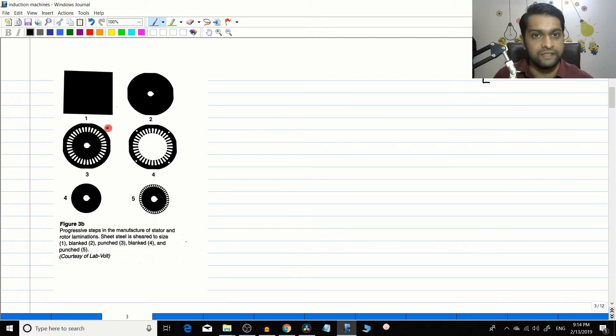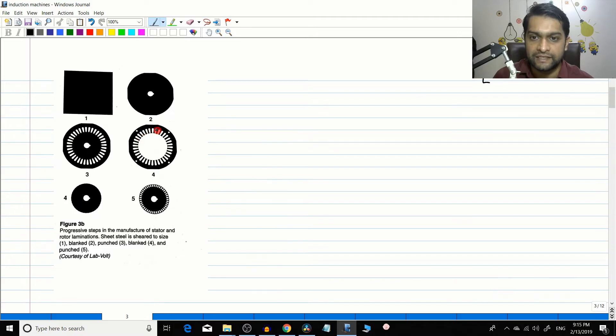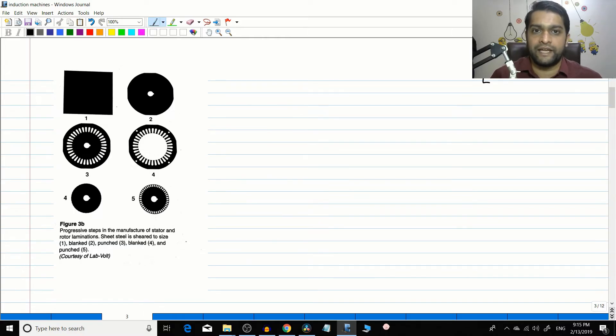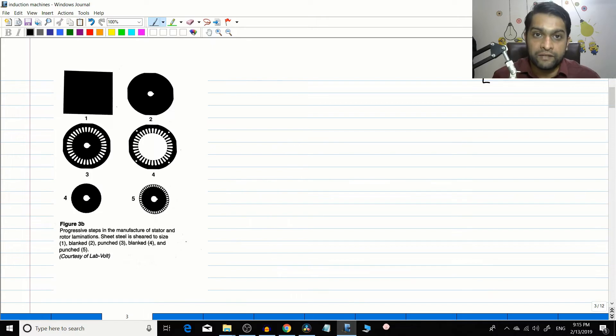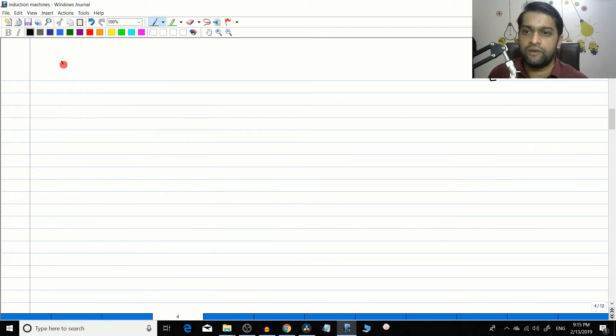Here are the basic stator construction stages. You start with a thin sheet of laminated electrical steel, punch out a single hole, and shape everything so that holes are evenly punched out. The entire inner section is punched out so you get a proper stator structure where stator windings can be housed. Many such laminations are stacked and riveted together to form the final stator structure.